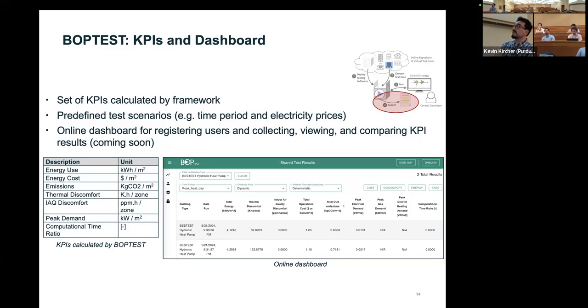And this is aided by the fact that apart from that KPI calculation, BOPTEST comes with some predefined scenarios for its test case. For example, that could have a 2-week peak heating period, or 2-week typical heating or typical cooling. And that allows each control developer to test those cases in that period with those boundary conditions, so that other people testing a different controller with that same building can compare the results one-on-one, which has been a big pain point in general for literature on advanced control in buildings.